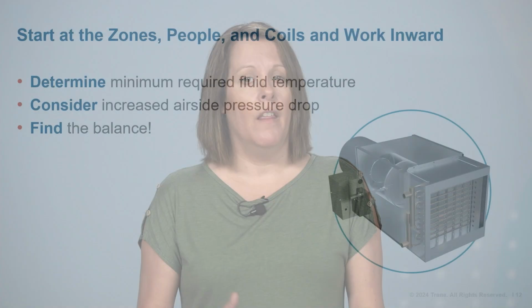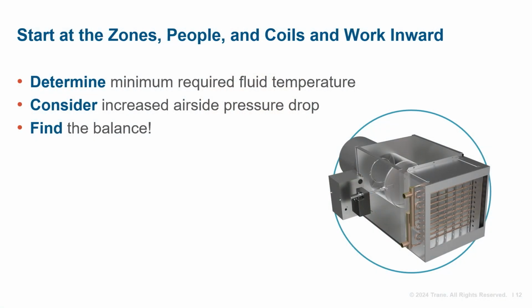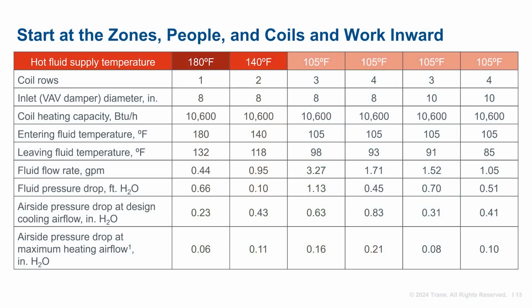By starting at the zones, we can identify the minimum required fluid temperature. Then consider the increased airside pressure drop and the potential need for increased flow rates. There's a balance to be struck there. Increased piping diameter may be required to accommodate additional flow, impacting valves and pumps. As an example, for VAV reheat coils, additional rows may be required. Let's look at an example terminal unit.